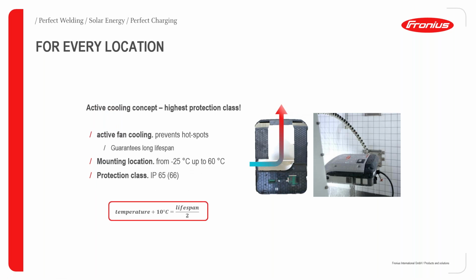It's an inverter made for every location, be it hot or cold, because it can be mounted in places of ambient temperature from -25 to up to 60 degrees Celsius. With an active cooling concept, it prevents hotspots and guarantees a long lifespan of inverters. It also has a high protection class, IP65 and 66 in some cases. There's one thing I'd like to bring to our attention here, the relationship between the temperature and the lifespan of inverters. For every 10 degrees Celsius increase in temperature, the lifespan of the inverter is halved. That is why we take the temperature coefficient very seriously, and work towards ensuring that the inverter operates optimally at all times.